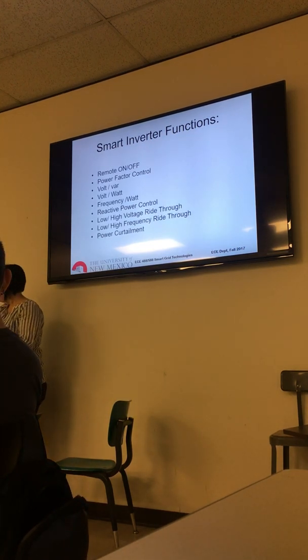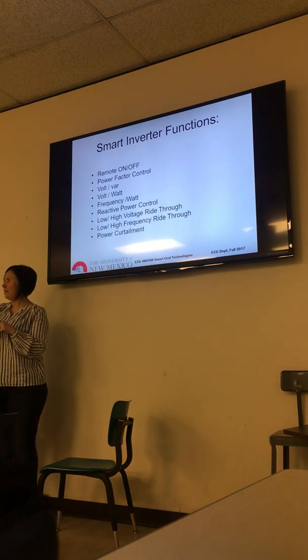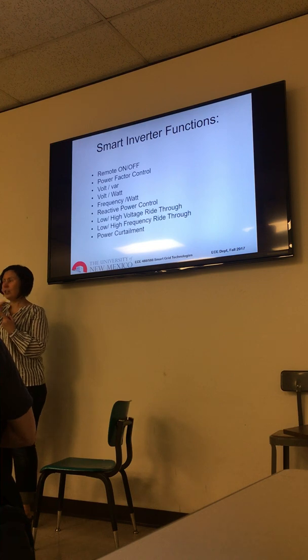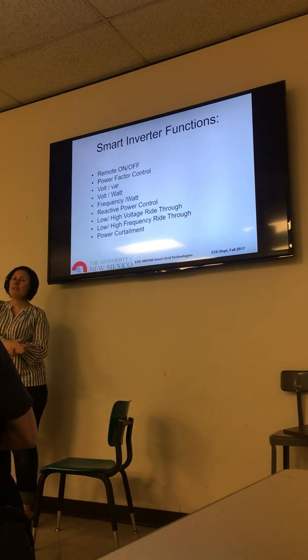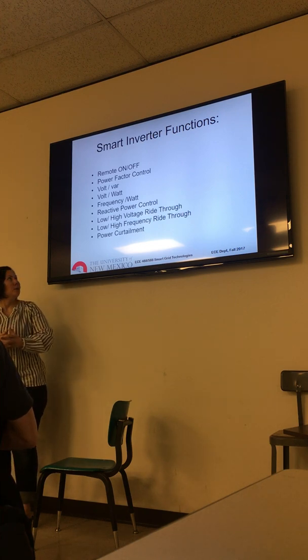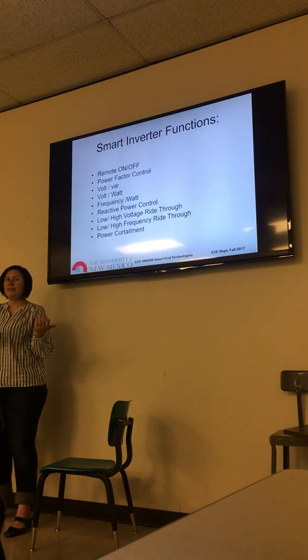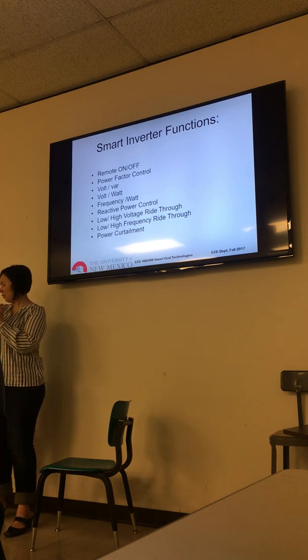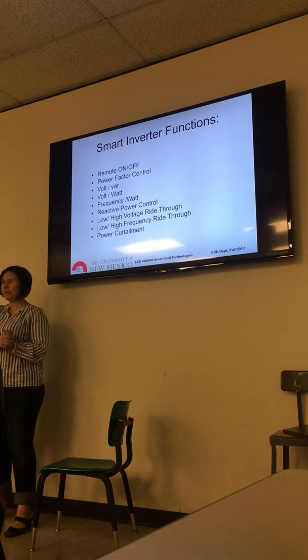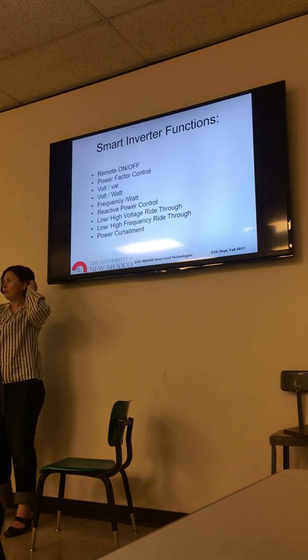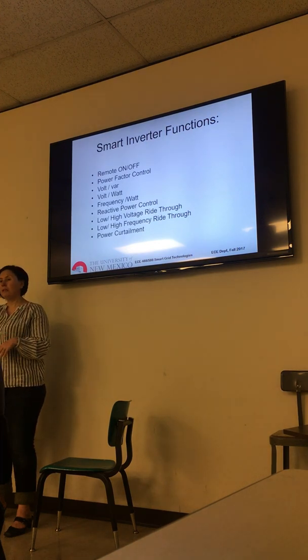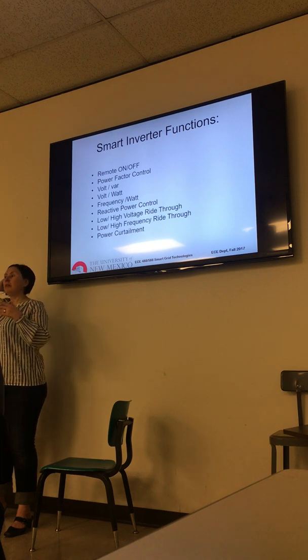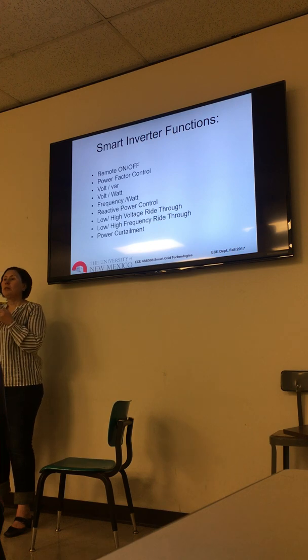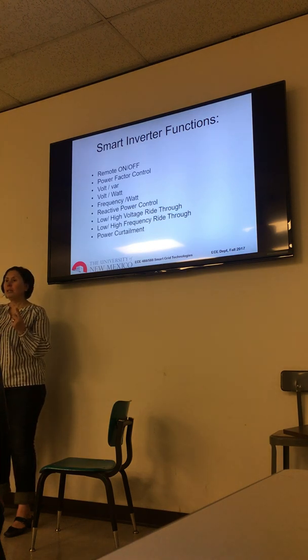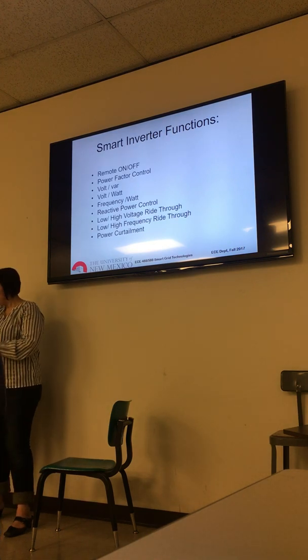So I'm still on point number 2, power factor. Previously, all of the inverters had one job in life, to take DC power and convert it to regulated AC voltage in that ANSI range, between those voltage levels, and at a fixed frequency: 60 Hertz for North America, 50 Hertz for Europe and other countries. That would normally translate into a power factor of exactly 1. For power system people, you know that reactive power is important, right? So sometimes you need a power factor that is not 1, leading or lagging, 0.7, 0.8. You may need reactive power control or reactive power compensation. So we should ask our inverter to provide a power factor that is not 1, but some other number. That is called power factor control.